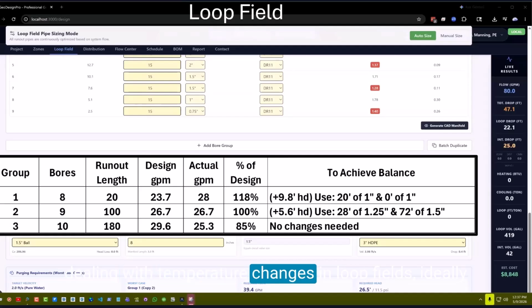And when we're dealing with temperature changes in loop fields, ideally it's about 6 degrees in heating, 12 degrees in cooling. In reality, the jobs I see are more like 4 or 5 degrees because we're over pumping the loop field. Let's say it is 12 degrees in cooling. We're going out at 95 and coming back at 83. If we've got the balance across those three loops, the temperature change is going to be roughly 10 degrees on group one and maybe 14 degrees on the third group. But when they all come back together again and mix within that return manifold, it's going to be that 12 degrees.